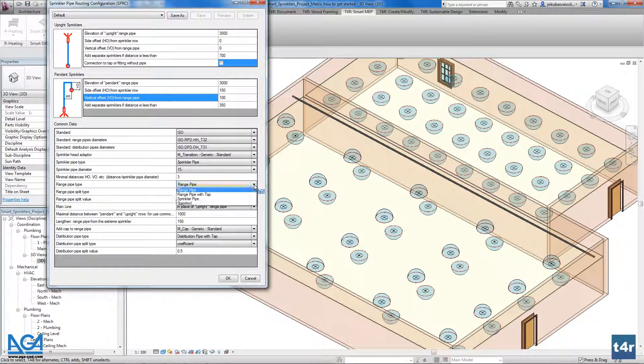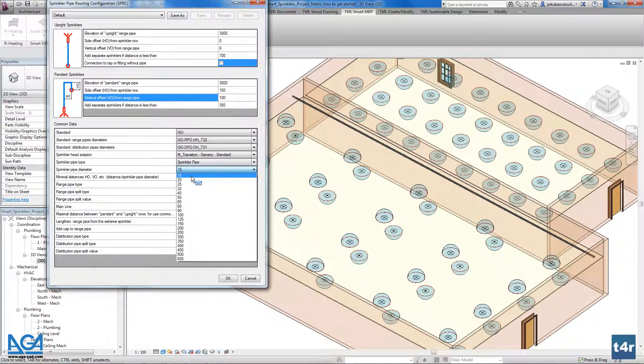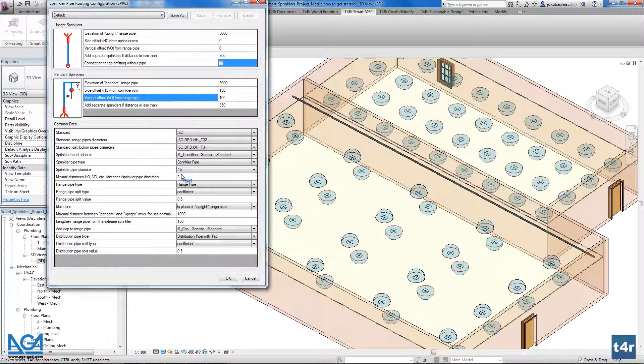We also have to define the pipe types: for the sprinkler we have the sprinkler pipe, for the range pipe we have the range pipe, and for distribution we have the distribution pipe. The sprinkler pipe diameter is the diameter of this pipe, and you can choose from all the diameters loaded into the family. The minimal distances H-O and V-O represent coefficients showing how many diameters of pipe you can fit between pipes.